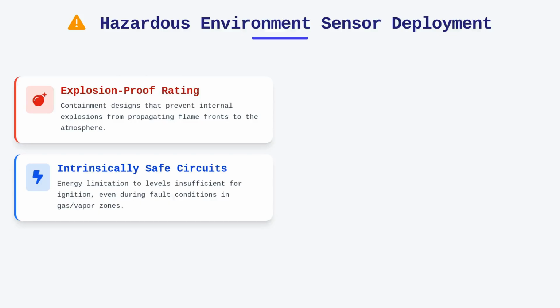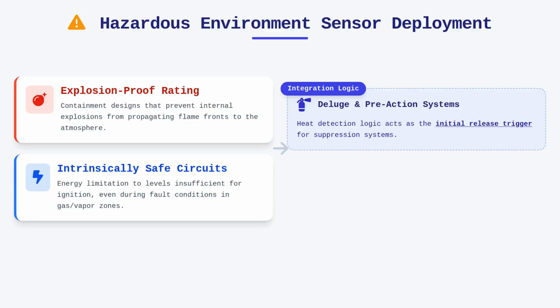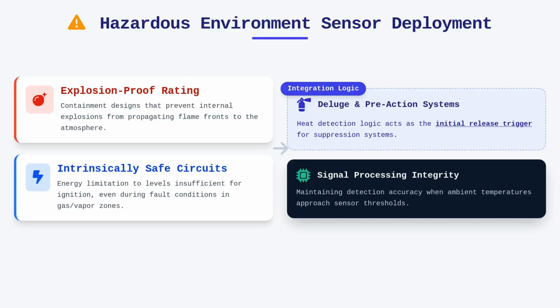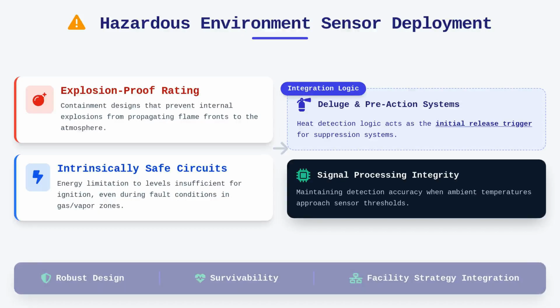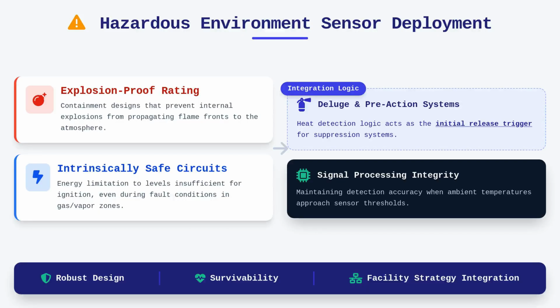These sensors often integrate directly with deluge or pre-action suppression systems, where the heat detection logic serves as the initial release trigger. The complexity of these systems necessitates a thorough understanding of signal processing, as you are responsible for ensuring detection integrity even when ambient temperatures approach the threshold of the sensor. The design must be robust, survivable, and perfectly integrated into the broader fire protection strategy for the facility.